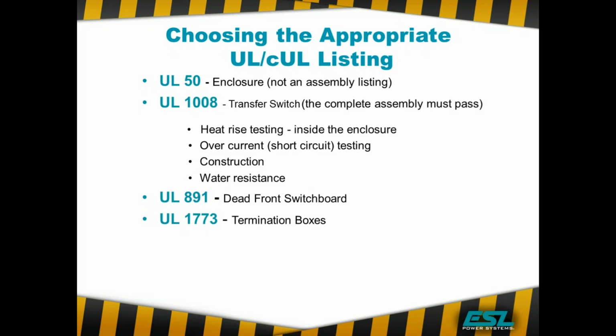As we get into this, a couple of things we want to keep in mind is how things are UL listed in the marketplace. Lots of products out there are listed as UL 50, and that really is just talking about the enclosure. So UL 50 says this enclosure meets a certain standard. It doesn't have anything to do about the assembly, doesn't say anything about how the thing functions, just the enclosure. We're going to talk a lot about UL 1008, which is the proper listing for a transfer switch, meaning a transfer switch that is transferring the source of power, not transferring between 2 panels, not transferring between 2 different circuits. It's about transfer of power.